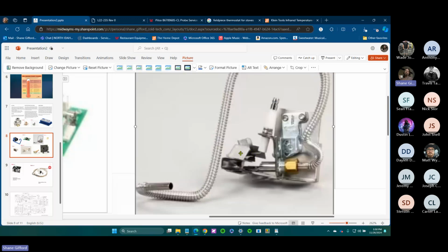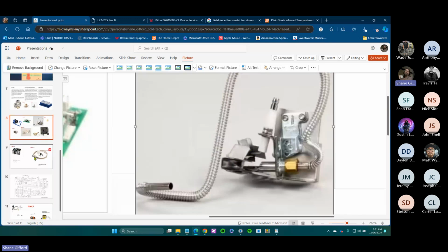And then oftentimes, in order to get that pilot flame to stay lit, if anybody has lit a gas fireplace before, you've got to light it, but then hold it. You've got to manually hold it so that pilot valve stays open and you're continuing to put gas through there. After about 30 seconds or a minute of continuous pilot hitting that thermocouple, you should be able to release the pilot and flame should hold, and then you're good to go. If you have one where you light it and you've been holding it 2-3 minutes and as soon as you release the button you lose your flame, then I would be looking at you're not getting proper flame rectification. Your gas valve is saying you don't have enough volts DC to hold me open.